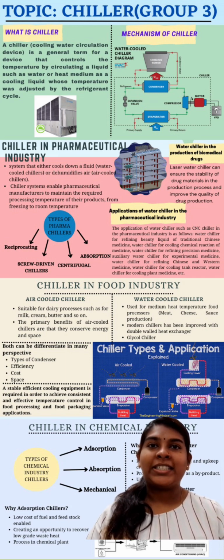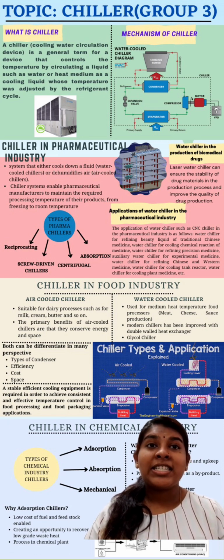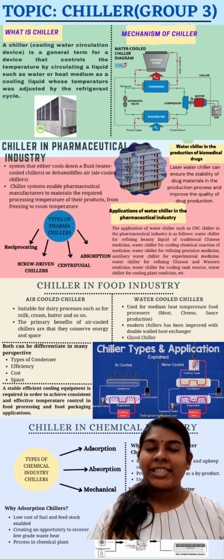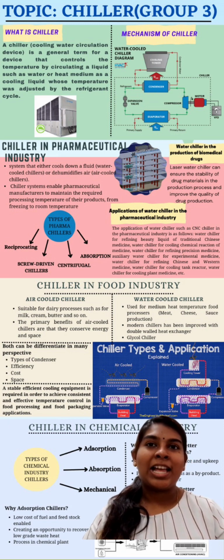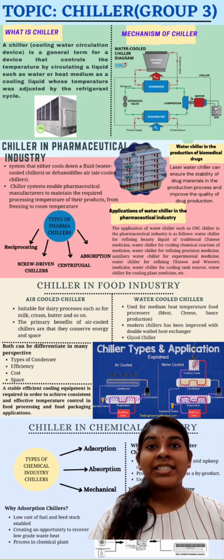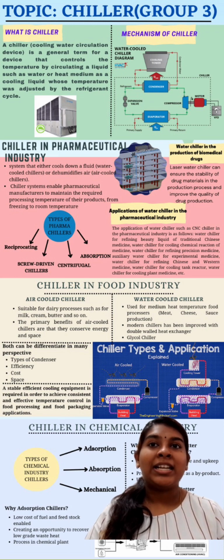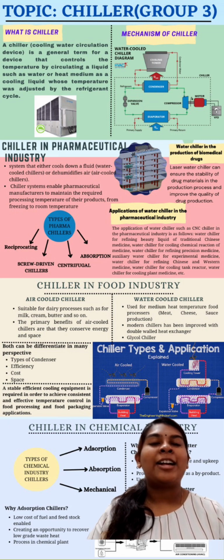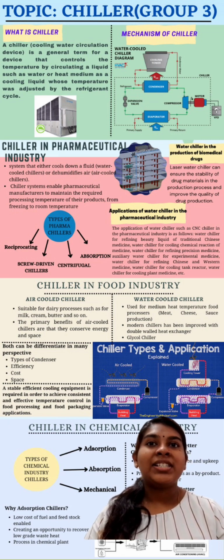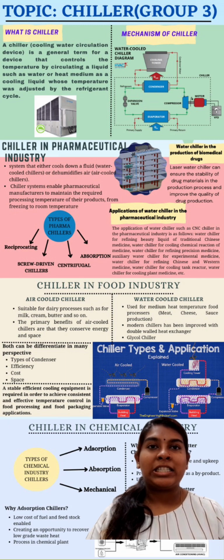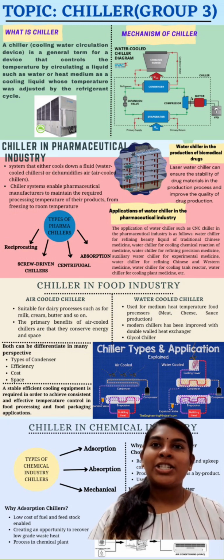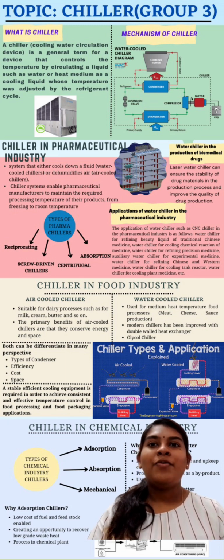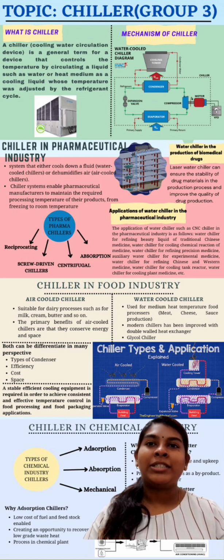Both can be differentiated in many perspectives such as energy consumption, efficiency, type of equipment, and so on. For example, a finned tube condenser is used in air-cooled chillers, while a shell and tube condenser is used in water-cooled chillers. In addition, the power consumption for water-cooled chillers is less compared to air-cooled chillers. Even though the initial and maintenance cost for air-cooled chillers is low, it depends on the application of the food industry. Now we are going to see specifically about water-cooled chillers.